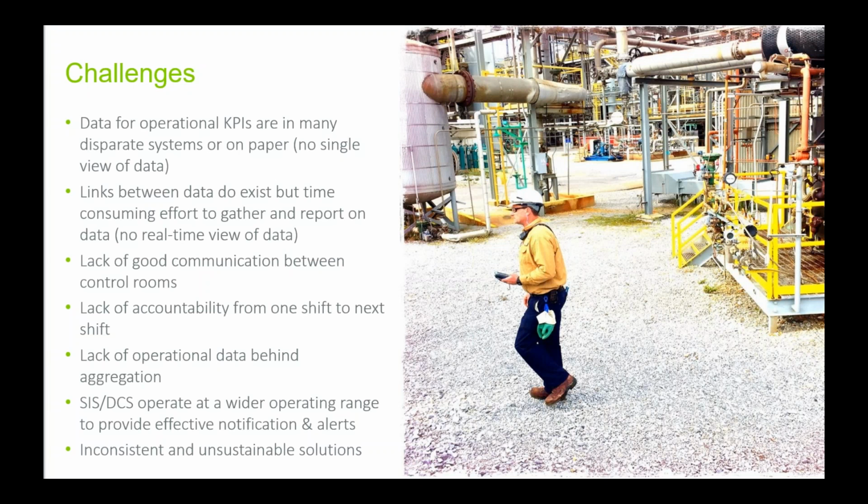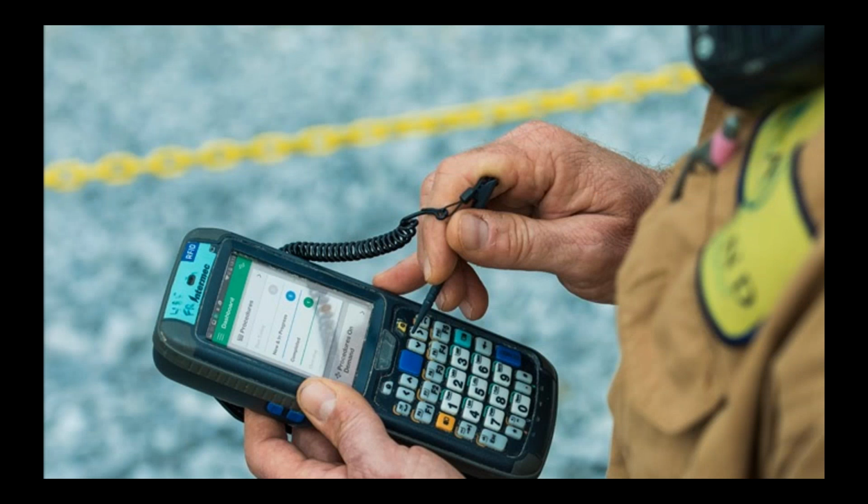So we programmed it explicitly: if the motor or the pump was down, the question would be asked, are the motor heater circuits pulled in for that pump? It would remind them to open the access port, and if the circuits were not pulled in, it would allow them to put in a work order or notification, or contact the high voltage shop to get it fixed. In the previous year, they had 9 events. They call them blue flash events, 480 volts to ground. It was apparently quite a memorable event, but maybe not memorable enough to remember to check every time. But that cost us $165,000 that year.